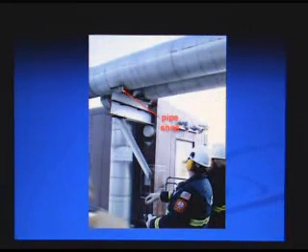And these are the insulated pipes. On insulated pipes, you can't put the pipe right on the steel, that will ruin the insulation, because the insulation is not very hard, and it can't carry too much weight. So what they do is they put shoes on the pipes. They weld a shoe to the pipe, which is this one here, and they cut the insulation around it, and that sits directly on the steel. These we call pipe shoes.